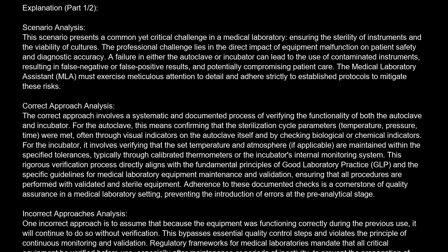Correct approach analysis. The correct approach involves a systematic and documented process of verifying the functionality of both the autoclave and incubator. For the autoclave, this means confirming that the sterilization cycle parameters, temperature, pressure, time, were met, often through visual indicators on the autoclave itself and by checking biological or chemical indicators. For the incubator, it involves verifying that the set temperature and atmosphere, if applicable, are maintained within the specified tolerances, typically through calibrated thermometers or the incubator's internal monitoring system.